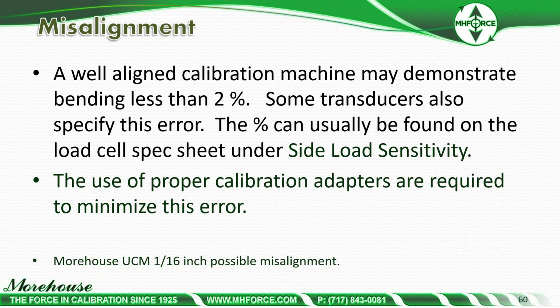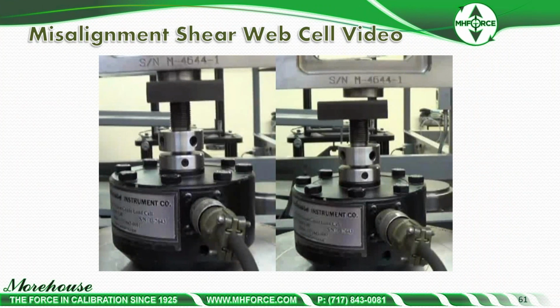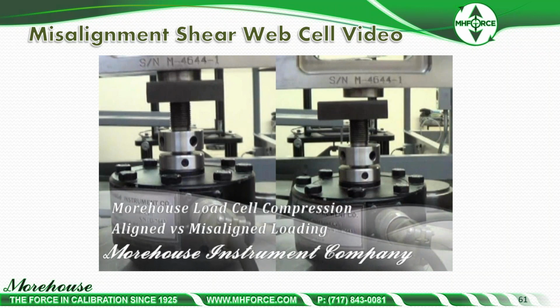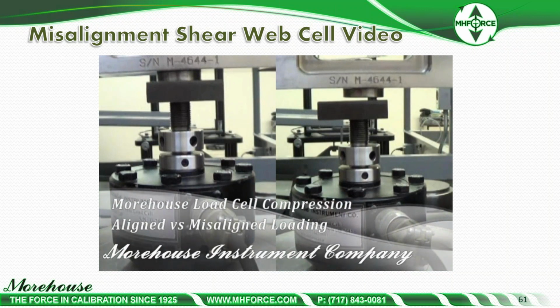And then a well-aligned calibration machine may demonstrate bending less than 2%. Some transducers also specify this error. We're looking here on the spec sheet for side load sensitivity. The use of proper calibration adapters is required to minimize this error. If you're using our UCM, a 1/16 of an inch possible misalignment equates to about a 30 parts per million error.